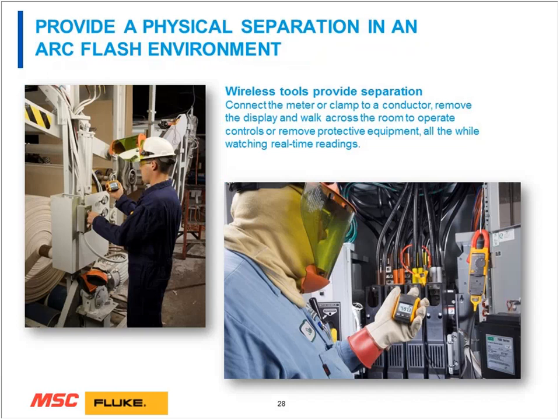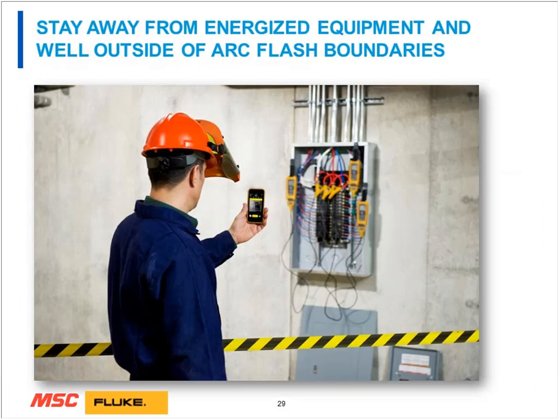You may consider providing physical separation for an arc flash environment. Anytime you can get out of the face of that cannon explosion that could possibly take place, you're better off doing it. So we have wireless tools, a variety of different ones, or some way to get a measurement outside the arc flash zone, away from a hot environment or a dangerous environment. So always use those. And stay well away from that energized equipment, well outside the arc flash boundaries.